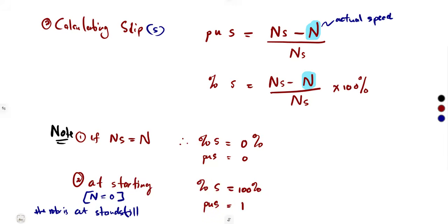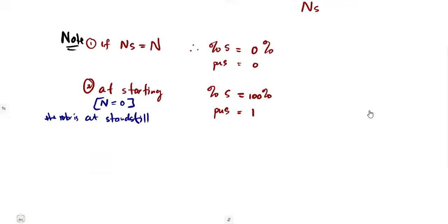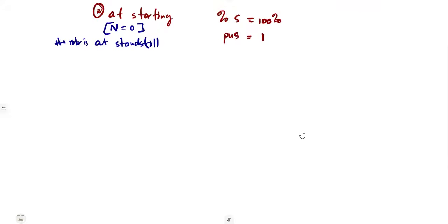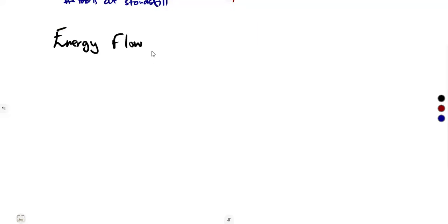All right, then also, guys, as we consider our induction motors, it is important that we do understand how power is being lost due to the losses that we have up to the output. So this is best described using the energy flow. It's another part which is very, very important in answering your questions. When you answer questions, follow the energy flow. So you've got the energy flow in a 3-phase induction motor.